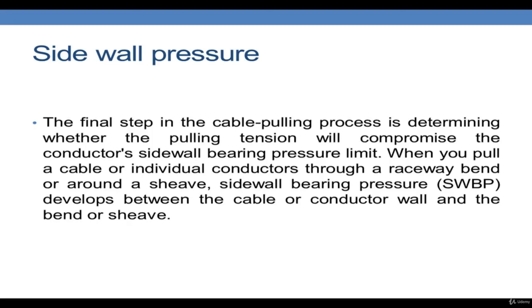And if we have very low tension on the cable, then this would potentially result in the jamming of the cable. So the cable pulling calculations are used to effectively optimize between these two tensions and get the cable pulled through the conduit without any damage to the conductor.